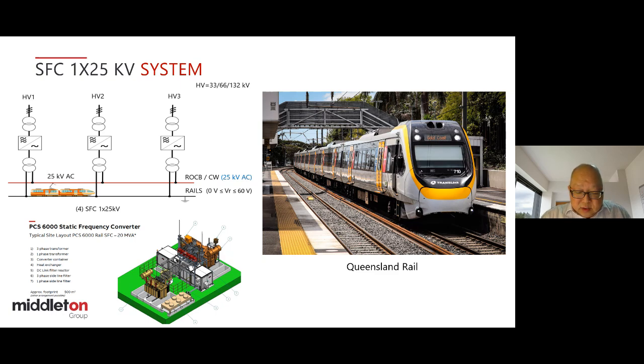And so what are the cons? Now, a traction transformer-based system allows an overload of, say, 150% up to 2 hours and 300% up to 5 minutes. Static frequency converter, you don't have that. You have to pay for it if you want extra. So that's why sometimes you see non-standard size units being distributed to certain projects. For ABB, they come in 20 MVA per unit, so you can have as many as you need, bolted together in parallel to form one SFC feeder station. GE units come in 15 MVA per unit, and Siemens 12 MVA per unit.